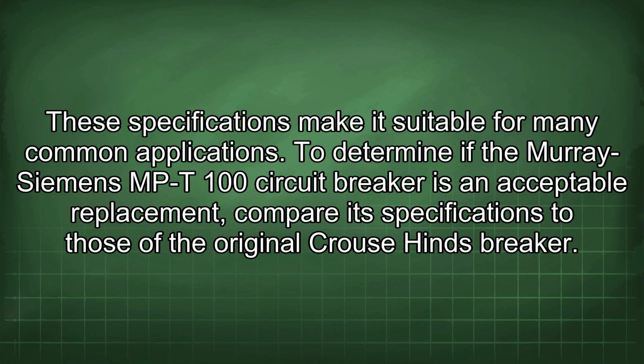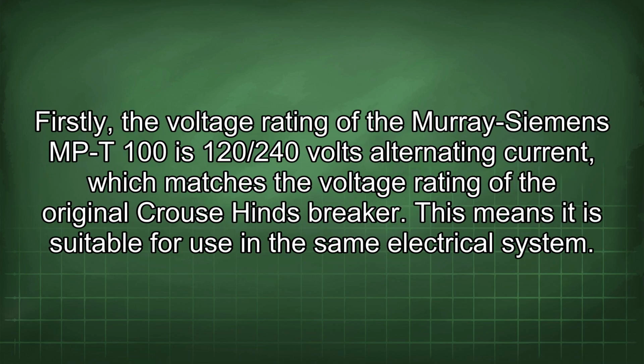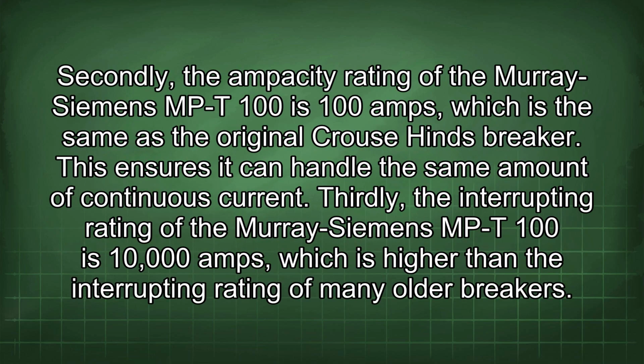These specifications make it suitable for many common applications. To determine if the Murray-Siemens MP-T 100 circuit breaker is an acceptable replacement, compare its specifications to those of the original Crouse Hinds breaker. Firstly, the voltage rating of the Murray-Siemens MP-T 100 is 120/240 volts alternating current, which matches the voltage rating of the original Crouse Hinds breaker. This means it is suitable for use in the same electrical system. Secondly, the ampacity rating of the Murray-Siemens MP-T 100 is 100 amps, which is the same as the original Crouse Hinds breaker. This ensures it can handle the same amount of continuous current.